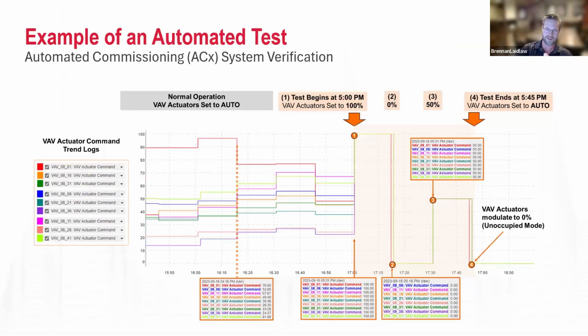So here's an example of commissioning VAV boxes, which are little dampers that open and close to allow more heating or cooling airflow. In this example, the automated commissioning system will pick a time of the day and set a certain number of VAV boxes to 100%, and it'll look at, say, what the airflow is coming out of them. Then it'll set it to 0%, and see, okay, is it actually fully closed? Then it's going to set it to intermediate levels and see, relatively speaking, whether it's getting the in-between values that we're expecting in the system?